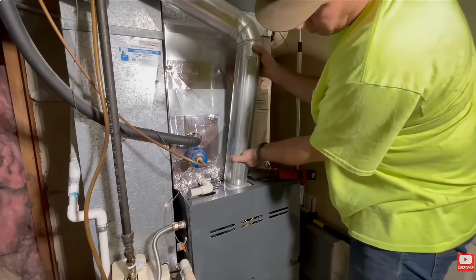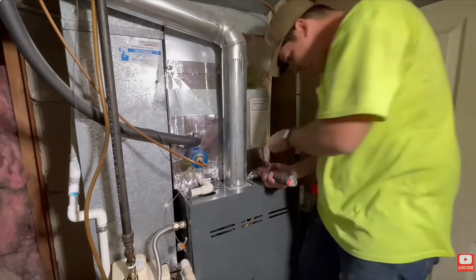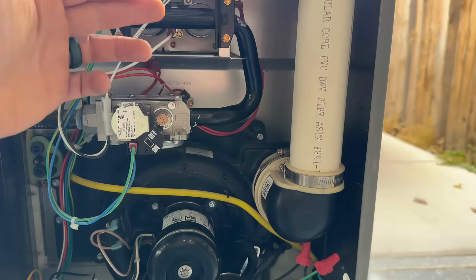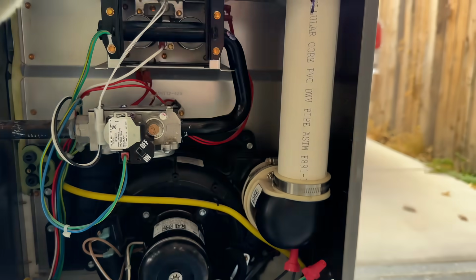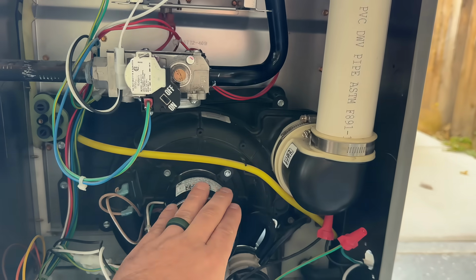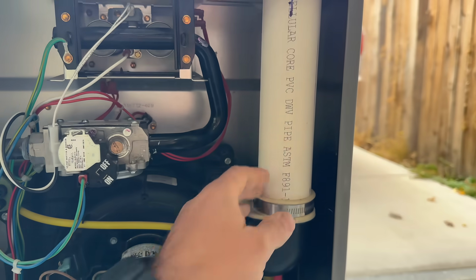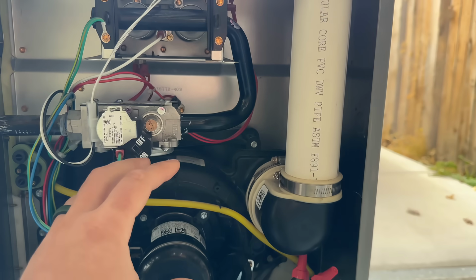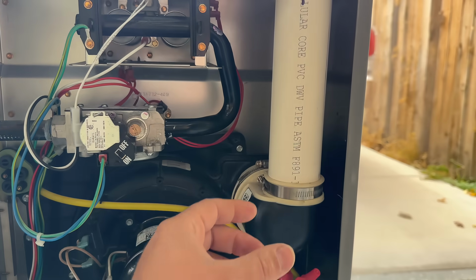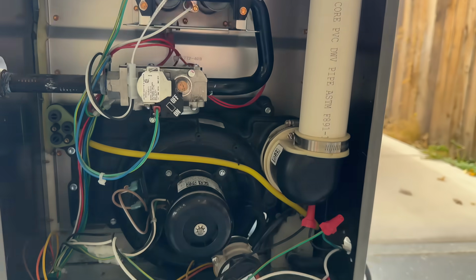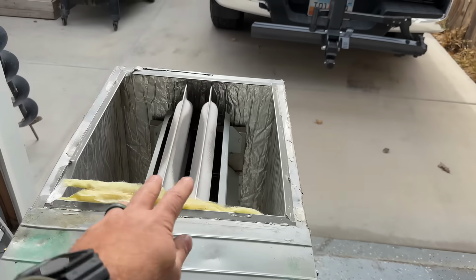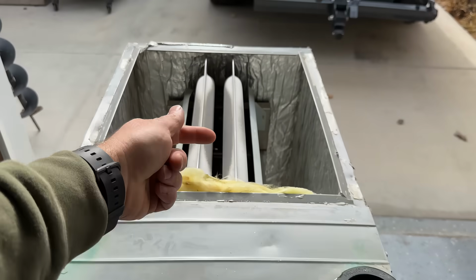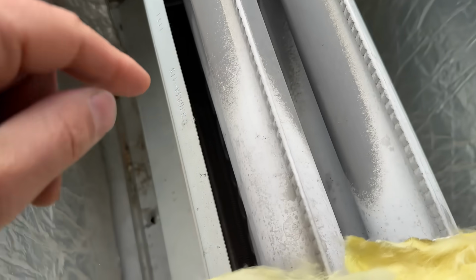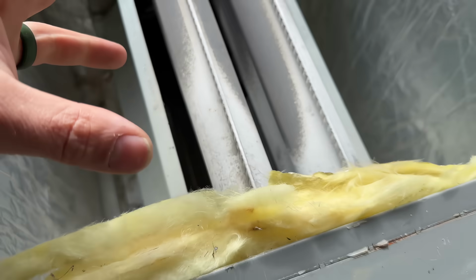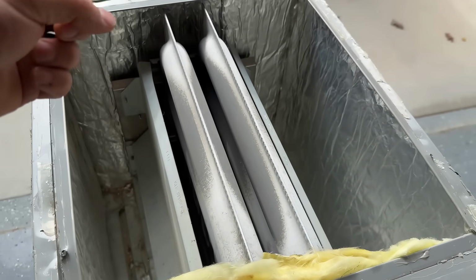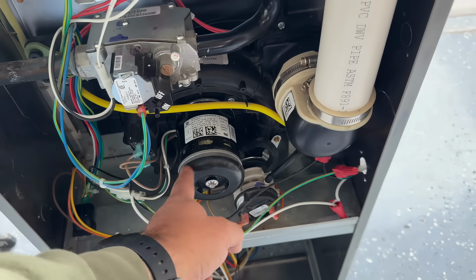That just means that you have a standard efficiency furnace, meaning you are going to burn 80% of the fuel that's sent in here. 20% is going to be pulled out by the inducer motor and it goes out of that metal vent. This is considered high efficiency. That's why it has PVC venting. It's burning 96% of the fuel, and it's pulling out about 4%. That's what goes out the exhaust. Now, this heat exchanger, where those flames go in, is all attached. So it goes through this first heat exchanger, then it goes through the secondary, which condenses water. It's pulling out so much heat that it condenses, and then it's getting sucked through the inducer and out.